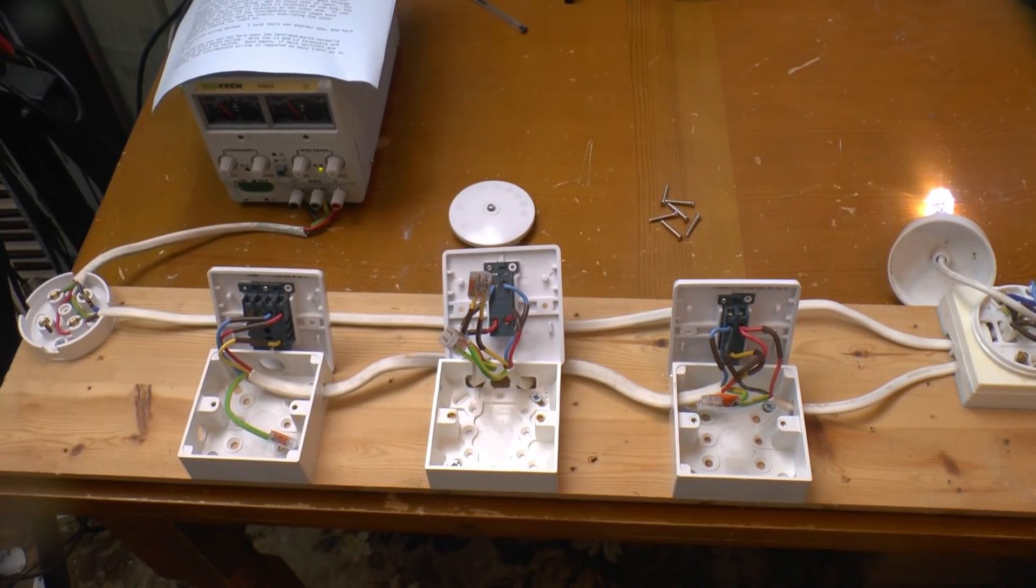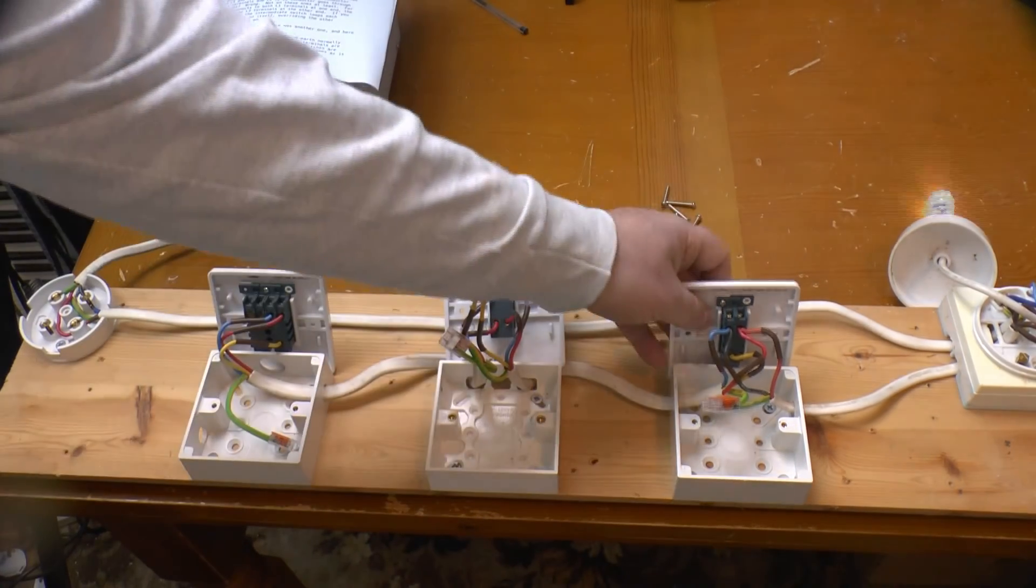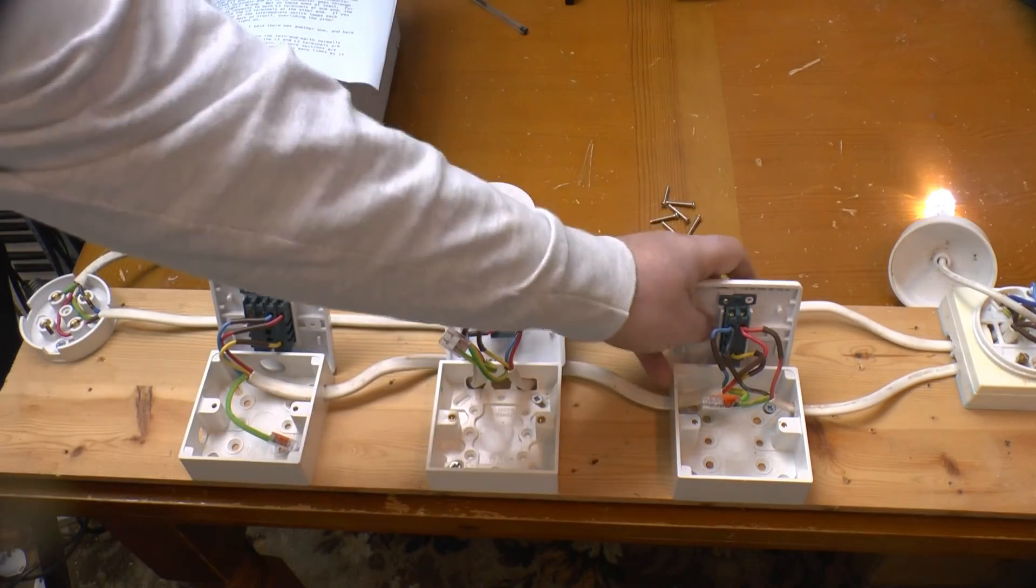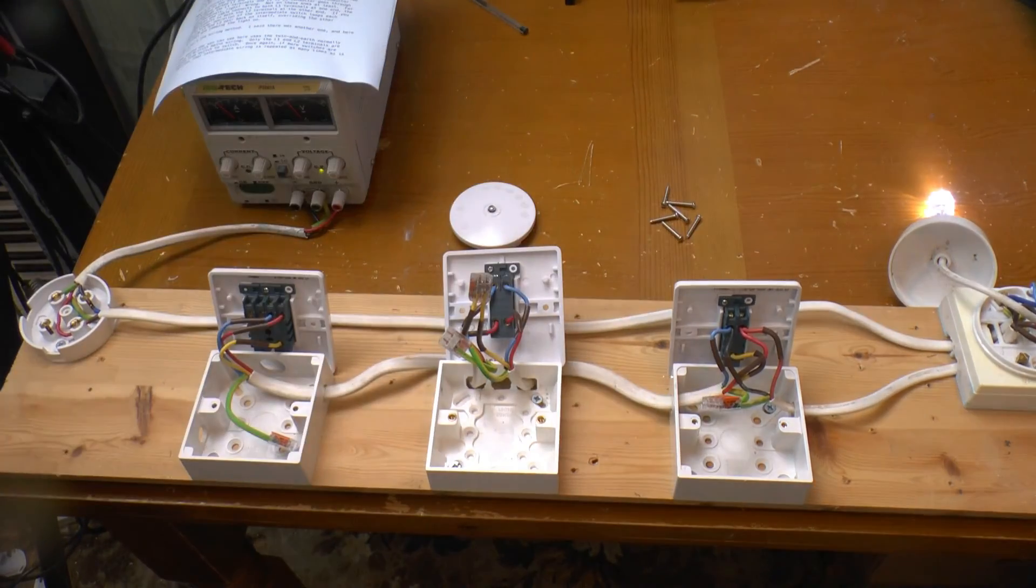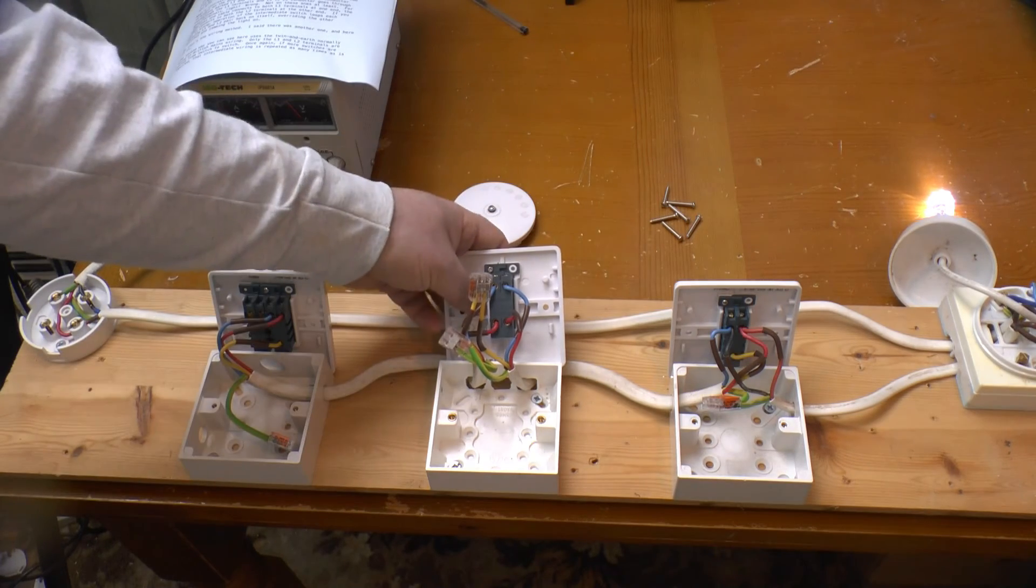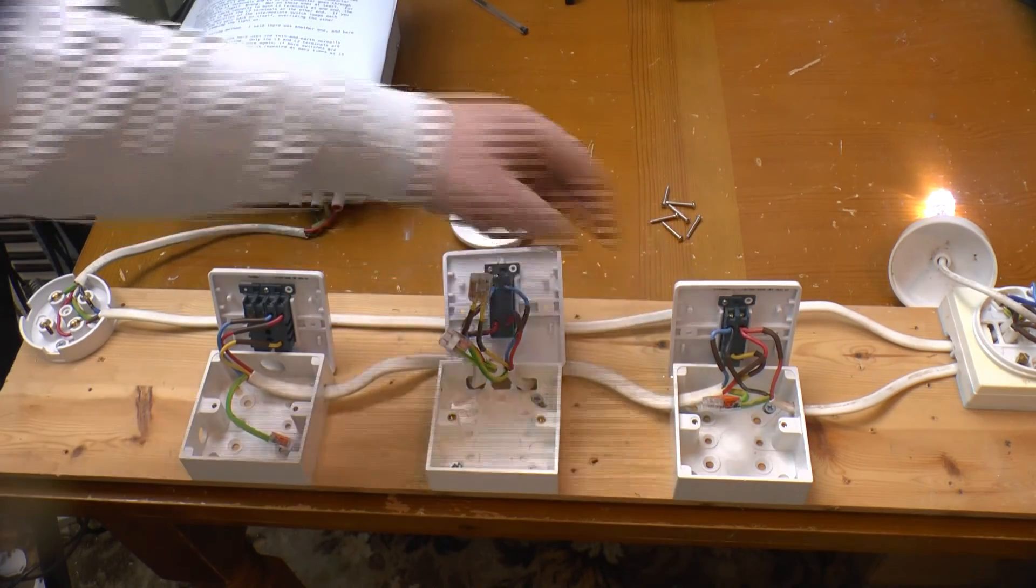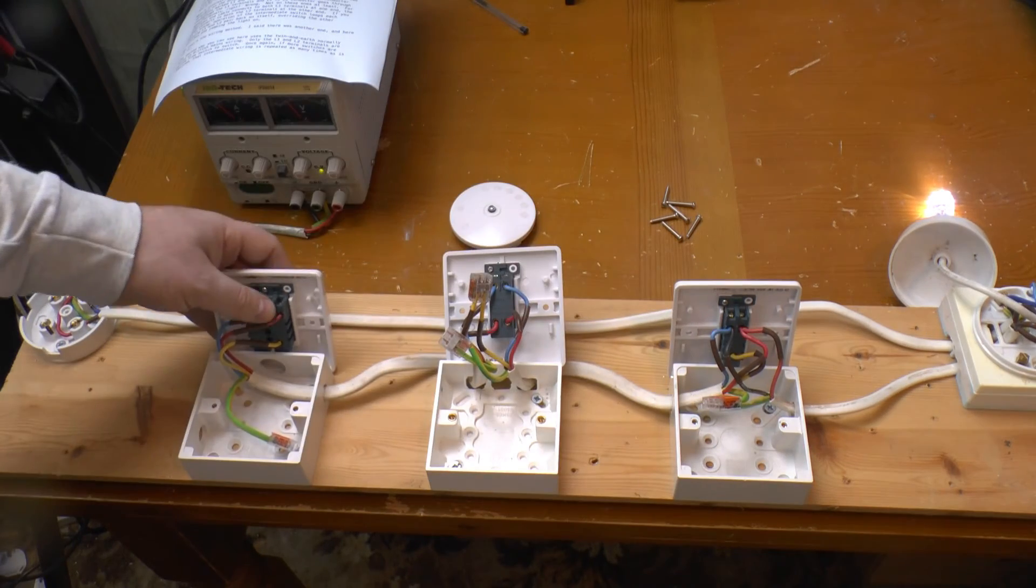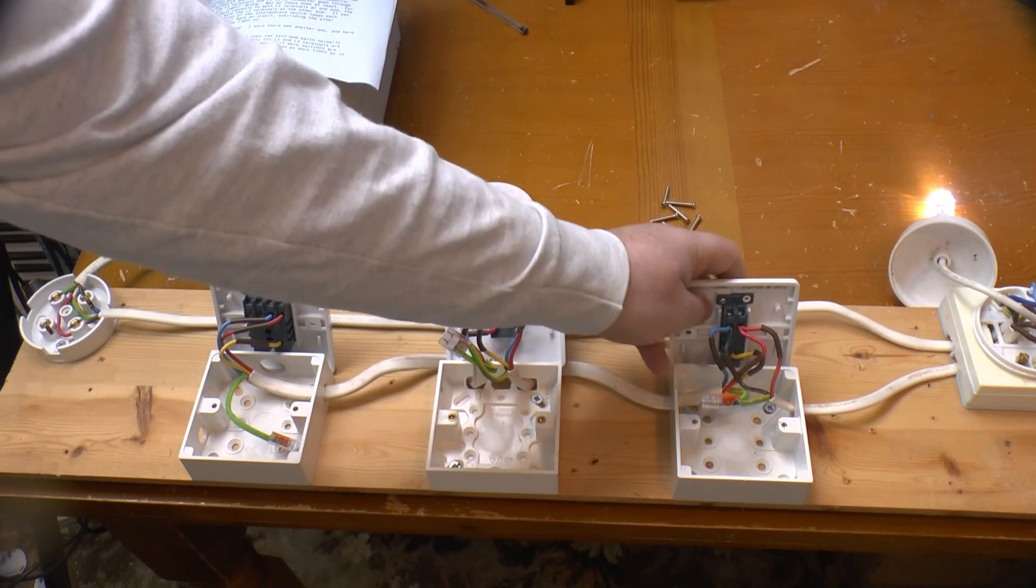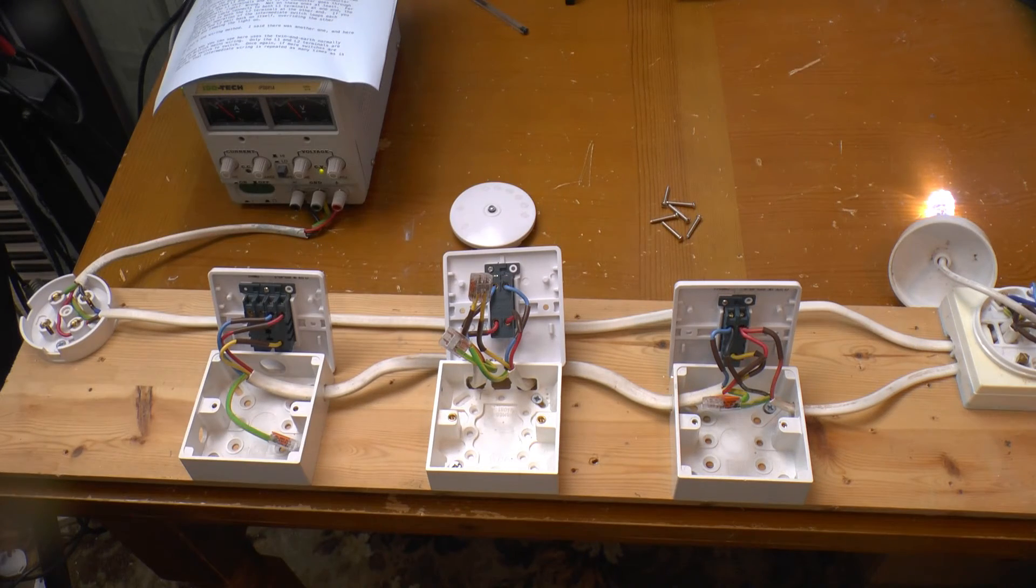And whereas in one position, the two-way lighting circuit will behave as normal. In the other position, it will join L1 and L2 together, override the other switches and jam the light on.